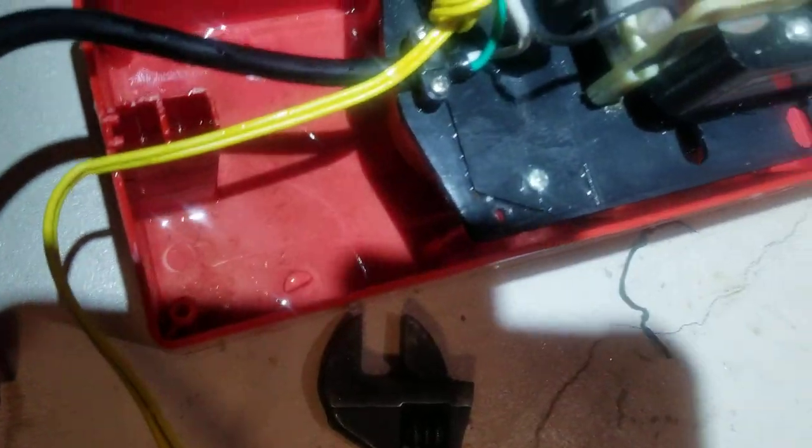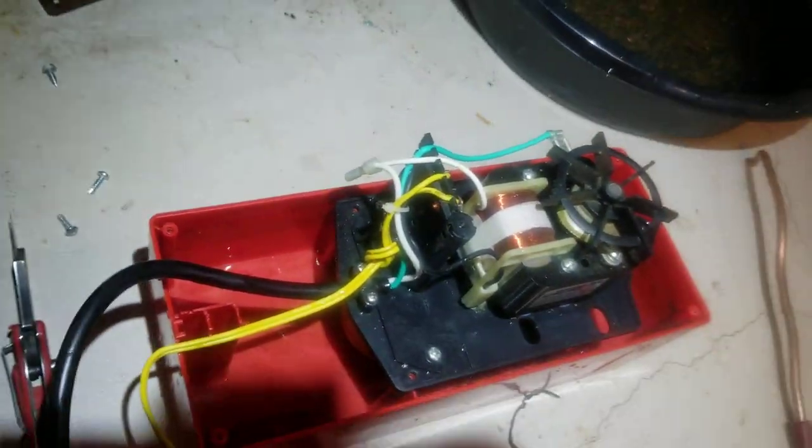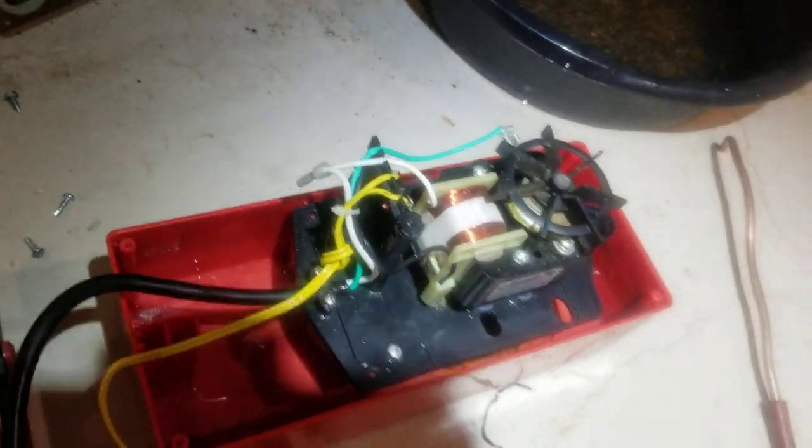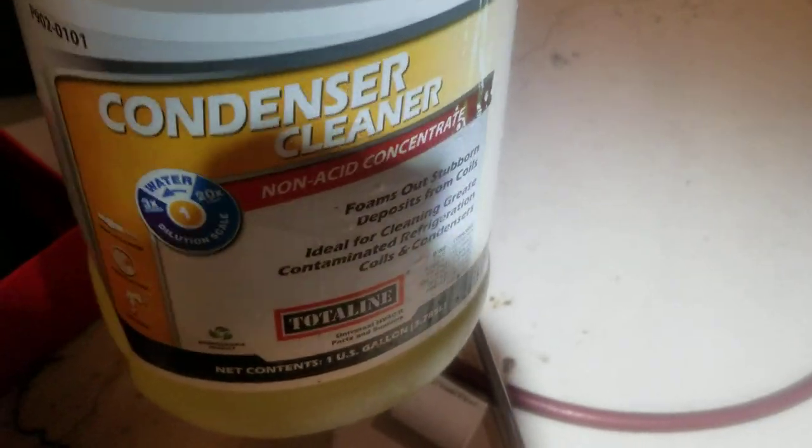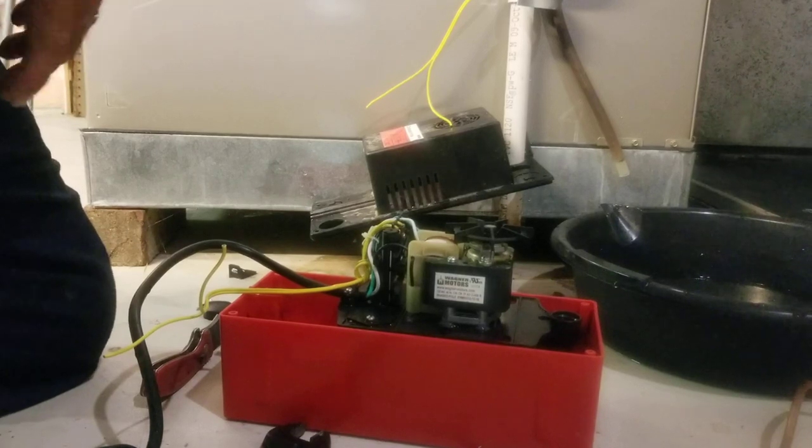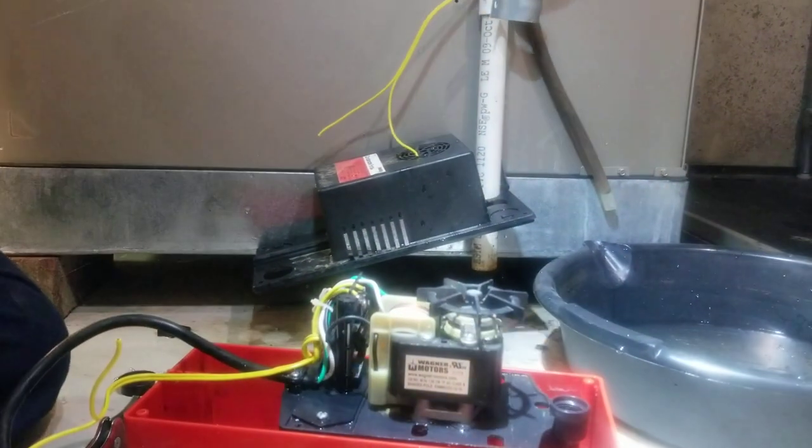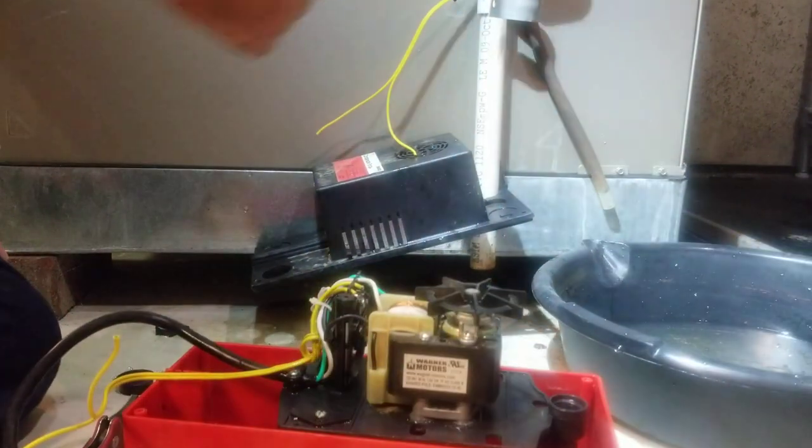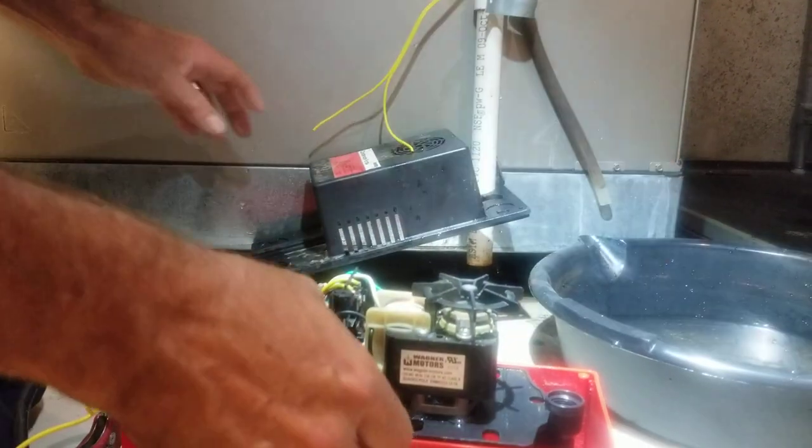Okay, we got it all cleaned out. My condensate pump cleaner of choice is condenser cleaner, hot water and condenser cleaner. It cleans it right out. And we'll add a little when we put everything back together just to kind of clear that line up.